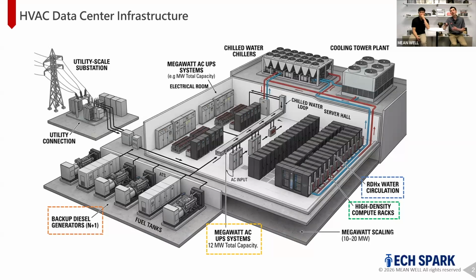On the right hand side you see a lot of high compute racks - those are the servers where the GPU, CPU, and power supply are built in, and that's where all the heat is generated. Therefore there is a lot of cooling. You see the red and blue lines - those are the liquid cooling, which circulate the heat out of the data center into a chiller. The heat exchanger is usually used to pull the heat out of the compute rack.